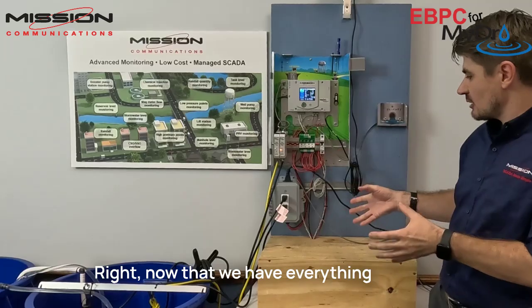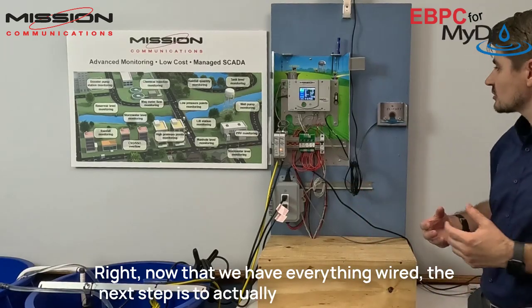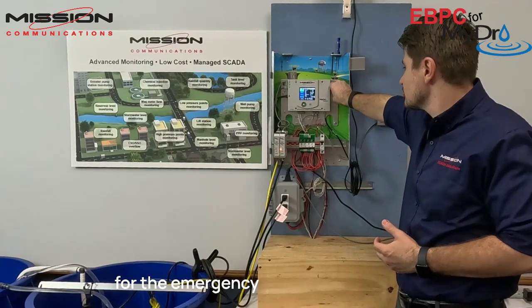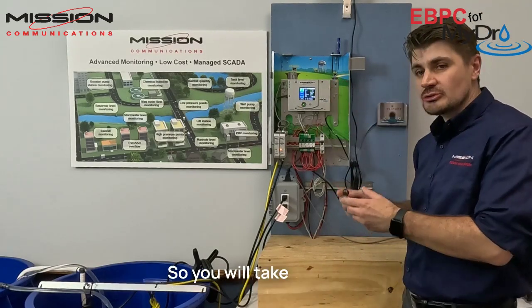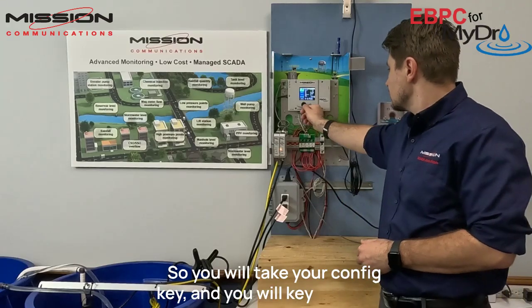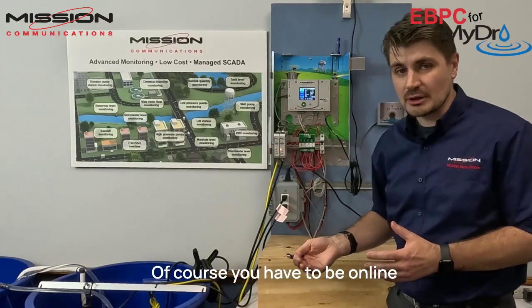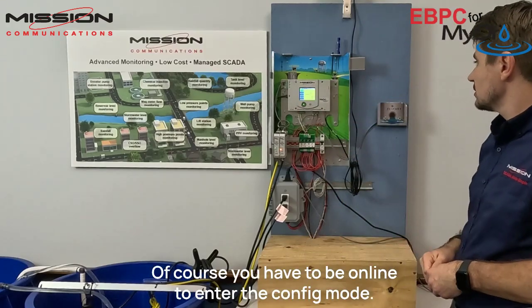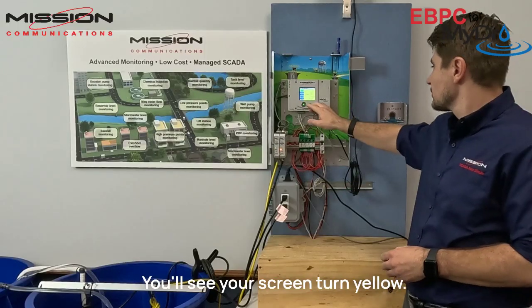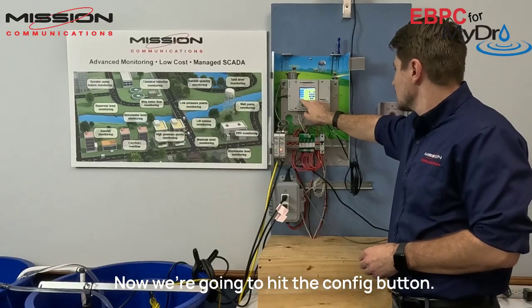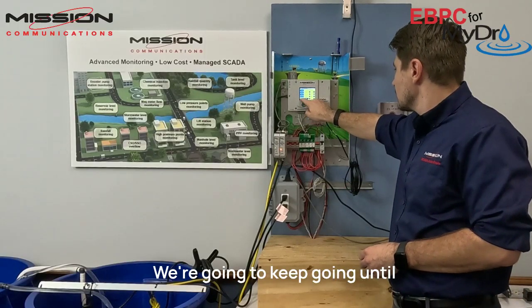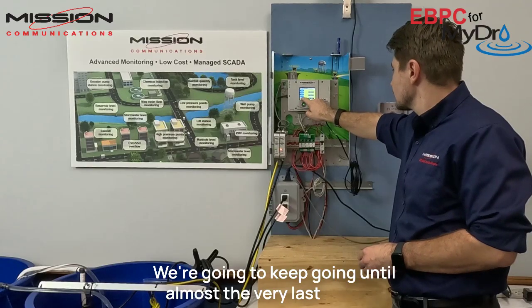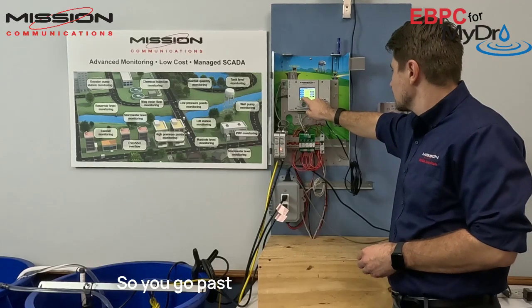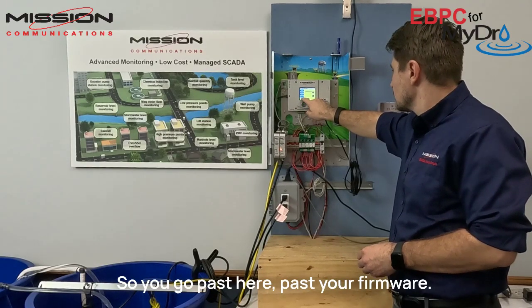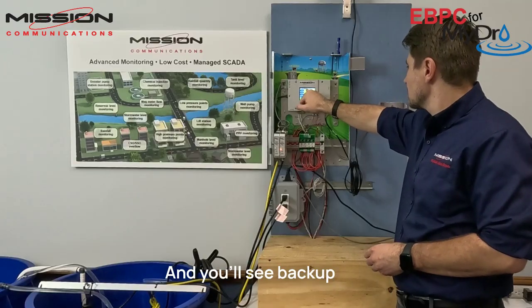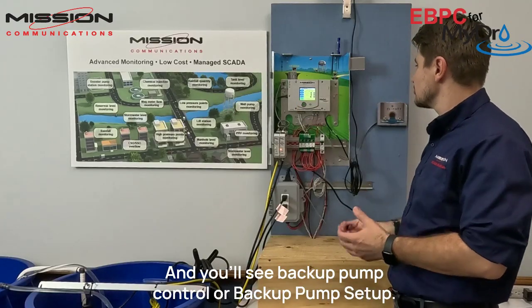Right, now that we have everything wired, the next step is to actually configure your MyDro for the emergency backup pump control. So you will take your config key and you will key your unit. Of course, you have to be online to enter the config mode. You'll see your screen turn yellow. Now we're going to hit the config button. We're going to keep going until almost the very last screen. So you go past here, past your firmware, and you'll see backup pump control or backup pump setup.